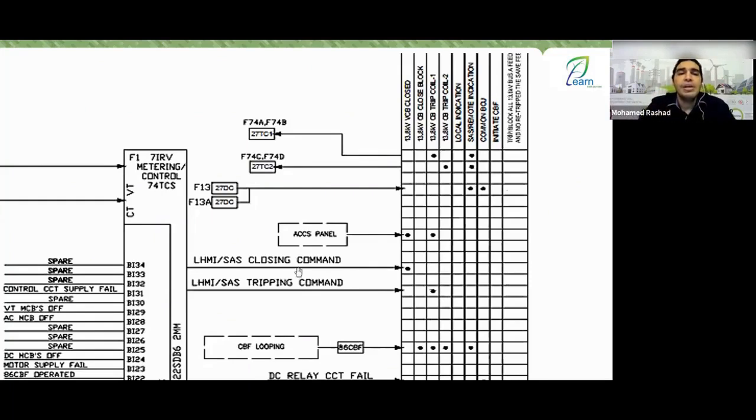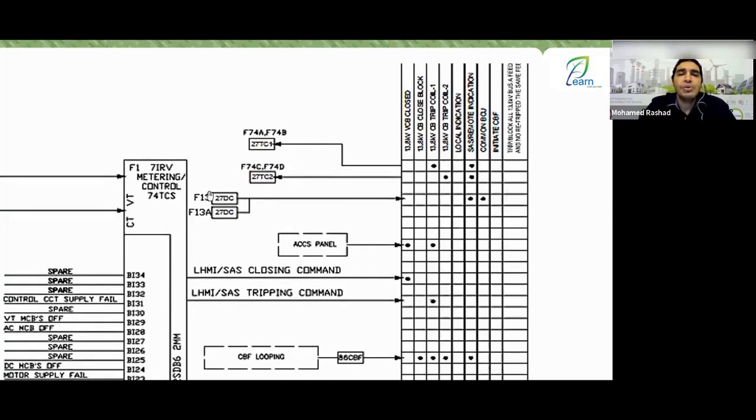Okay, for example, he comes and tells you you have something like 27 DC, which is DC supervision. Okay, DC supervision, is one of the two, 74 DC, which means supervision on DC. Yes, 74 DC means supervision on DC. Either 27 DC, and for people who understand protection, they know that 27 means under voltage on DC, meaning the quality of DC is low. You are saying the quality of DC is low, meaning there is a problem with DC.